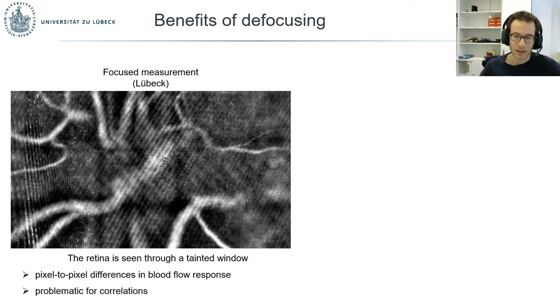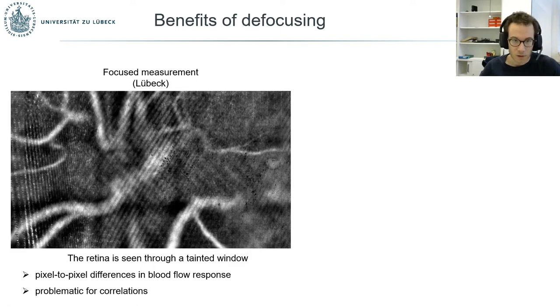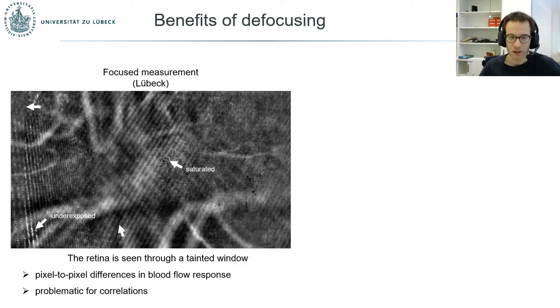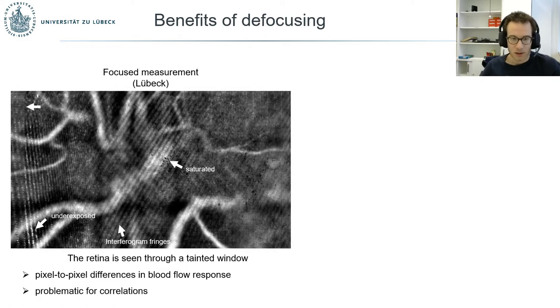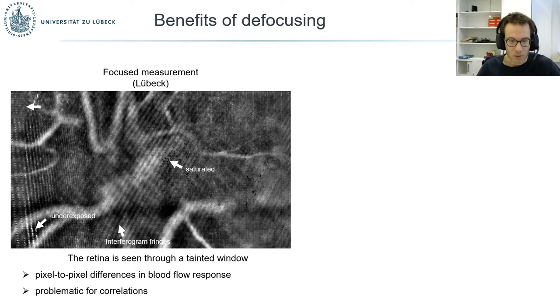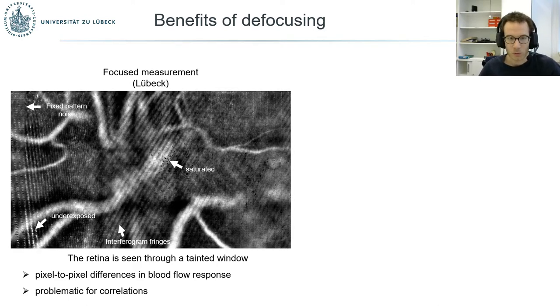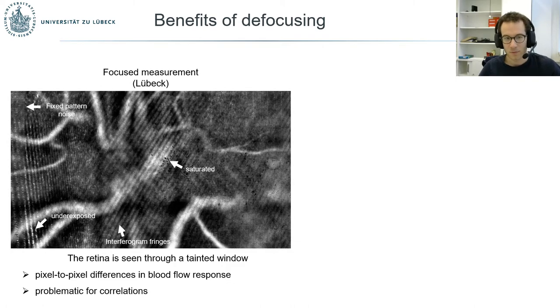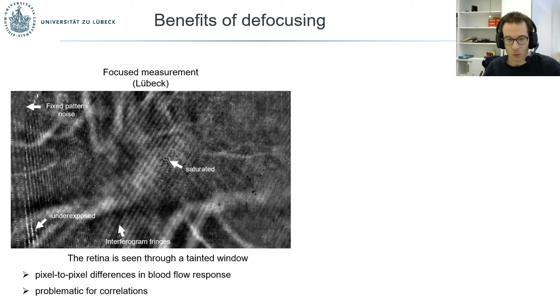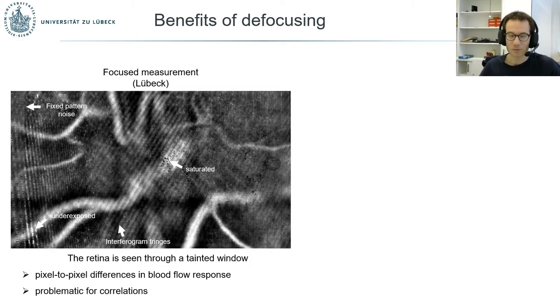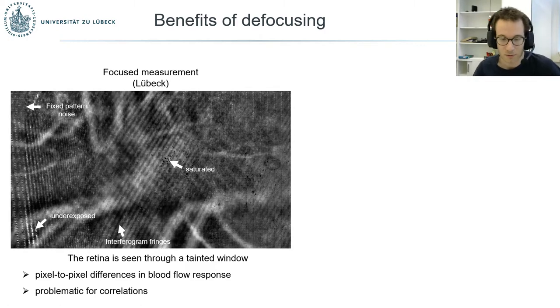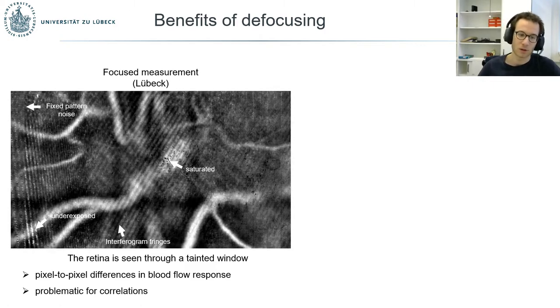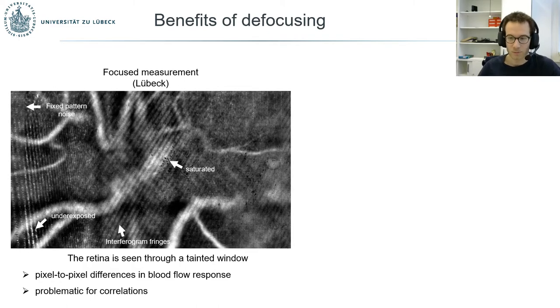These artifacts are particularly visible when the eye is moving. There are dead pixels — either white or black — because original pixels were underexposed or saturated, residual influence from the interferogram illumination, and noise with a specific pattern corresponding to sensor defects. It feels like the retina is seen through a tinted window, with residual pixel-to-pixel differences in blood flow response that are visually unpleasant and problematic for sophisticated processing such as spatiotemporal correlation analysis.